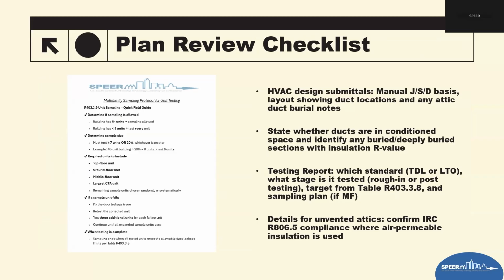So, trying to catch duct system issues on plans to avoid major inspection problems later. Design submittals should include a Manual J, S, and D and a simple duct layout. So they must review a complete package, J, S, and D. This ensures the system is sized and selected, and ducts are selected per size, correctly.